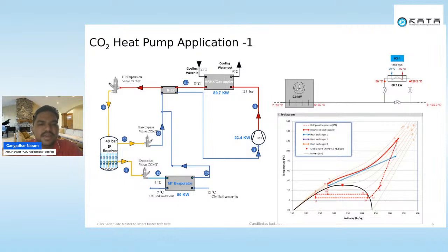Similarly, in the high pressure expansion, this cycle is already constant. We have already discussed this cycle. So this is your electronic expansion valve. At the electronic expansion valve outlet, my compressor is maintaining 40 bar suction pressure, saturation suction pressure, which is equal to 5 degree saturation temperature.